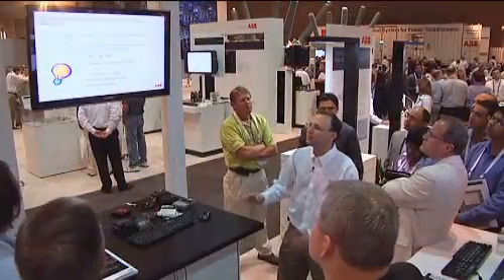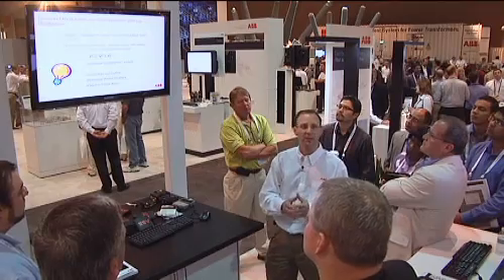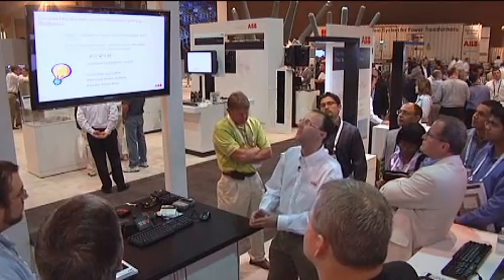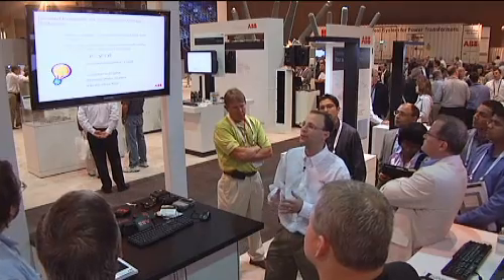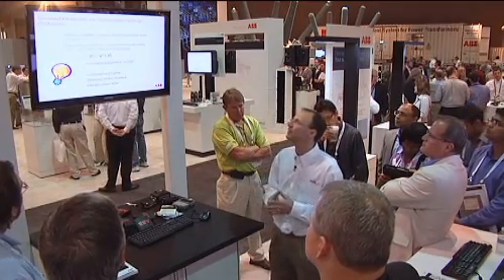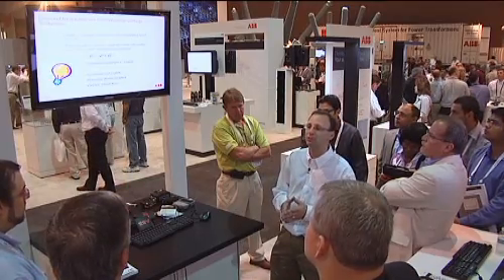And they deform the voltage profile, and we'll get into that later, but they result in a greater drop in voltage along the feeder. So that's VARs, and just correcting VARs alone is a very important and very worthwhile initiative. But in addition to that, the volt-var management system can reduce the demand by an approach called conservation voltage reduction.